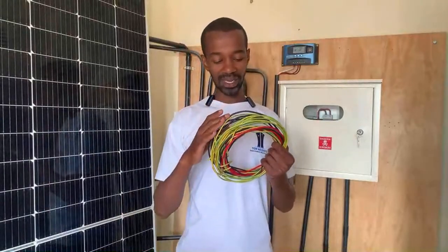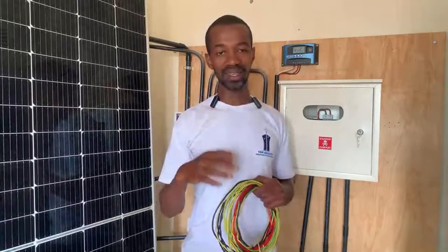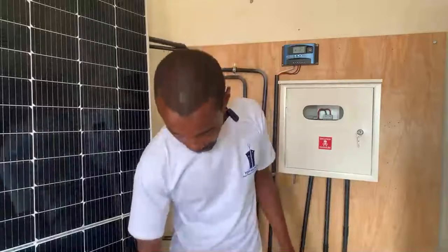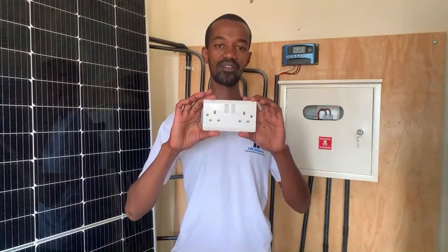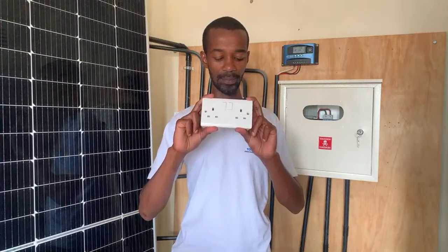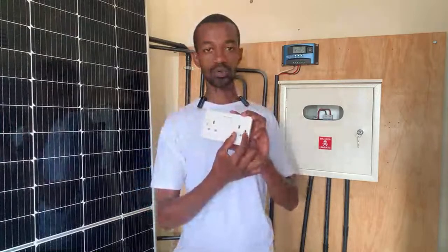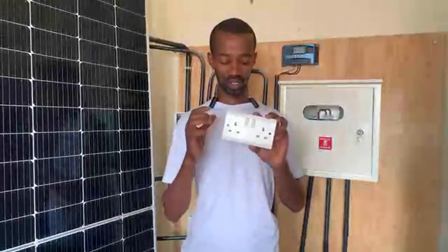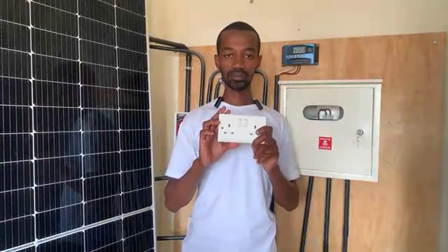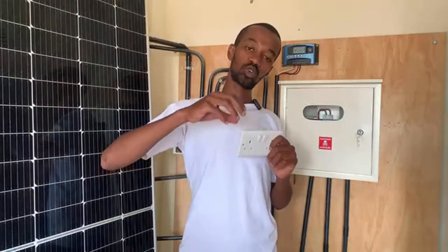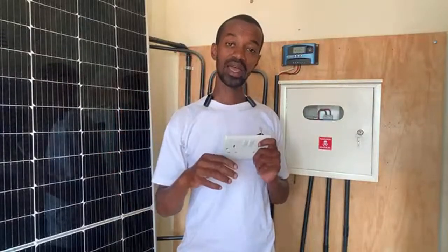This cable must not be less than 4.0 millimeter square when it comes to a heater or a microwave. When we talk about the kitchen socket, like I discussed in a previous video, you might find a customer has a twin socket wired in the kitchen. They'll connect something like a microwave here, and on the other socket they'll have an extension cord, probably a 4-way or 6-way, with several appliances connected at the same time. That means the combined current drawn from this circuit is a lot.